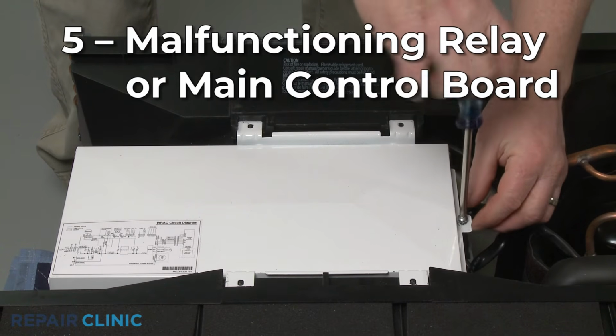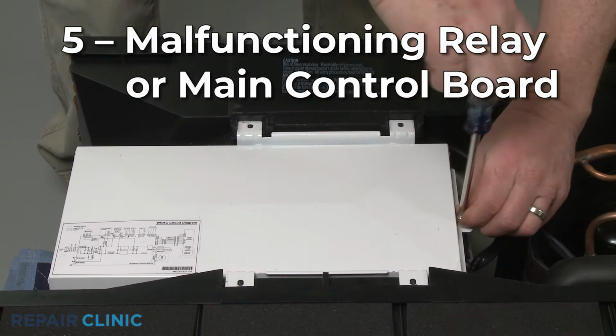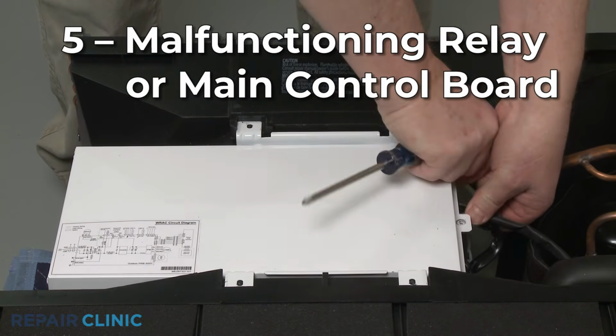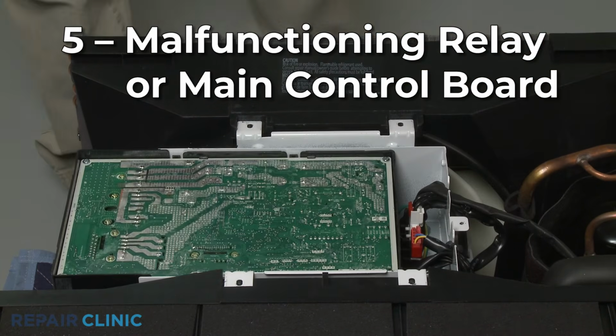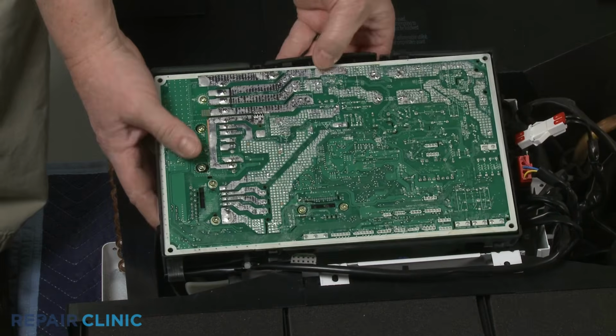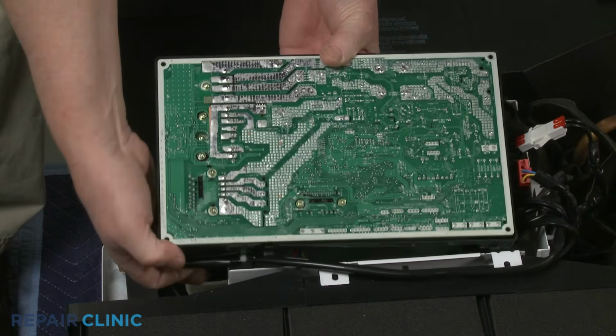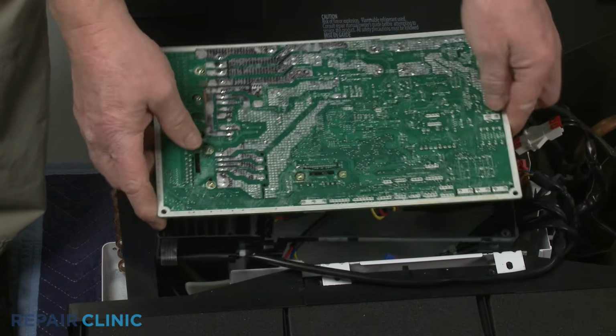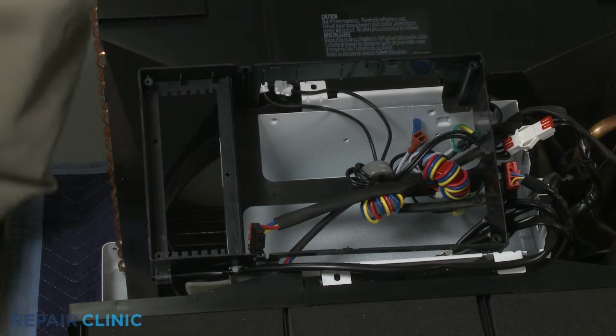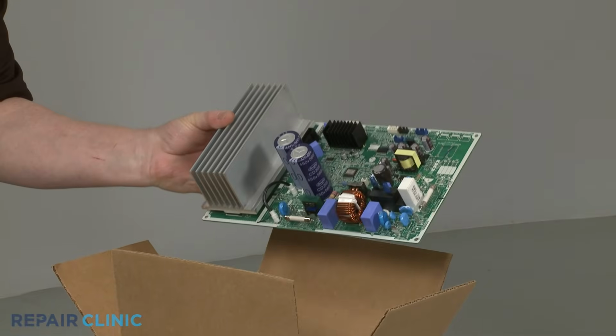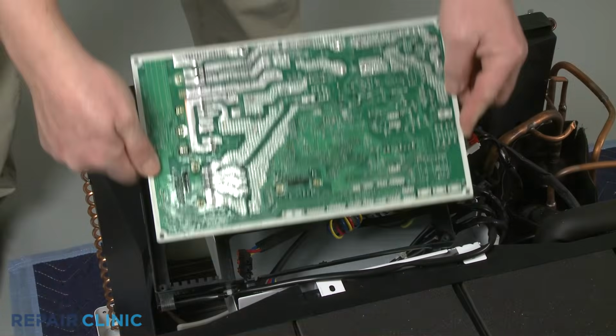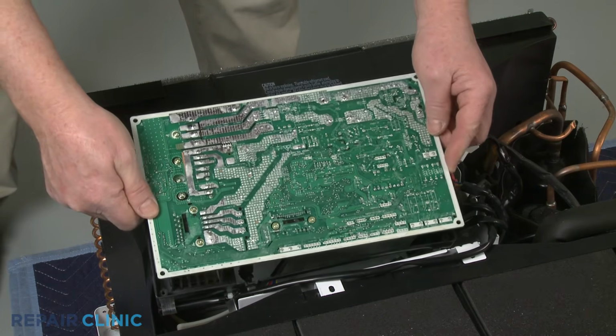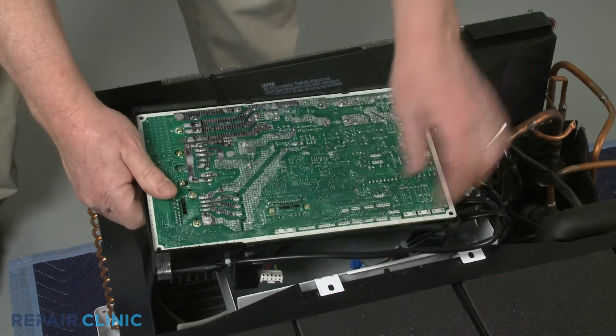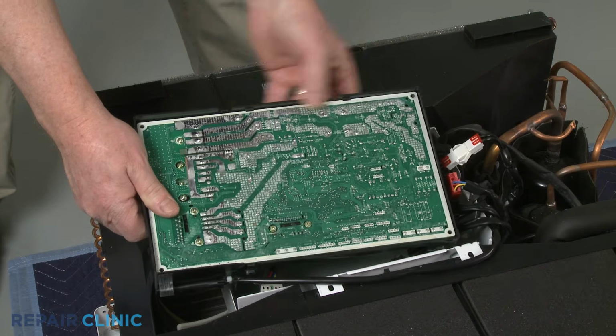Relay boards and main control boards provide voltage to many of the air conditioner's components, including the compressor. If the board is malfunctioning, the compressor may not be receiving the voltage it needs to run. Since this is not that common of a problem, you should verify the other more likely defective parts are working properly before considering a relay or main control board replacement.